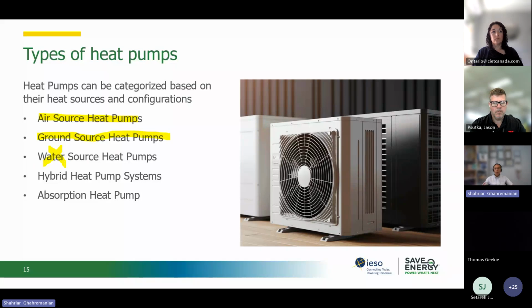So if we have a lake, and if the codes and the municipality allow it, water source heat pumps can be similar to the ground one, which means that we dig in the ground, but we are connecting to an underground water source, and then we use it for our heat pumps. The other heat pump type is the hybrid heat pump, and the last one is the absorption heat pump. Absorption heat pumps suit commercial buildings which require heating and cooling at the same time, or buildings that have access to low quality heating sources like process heat or anything else. Absorption might be a good option for them.